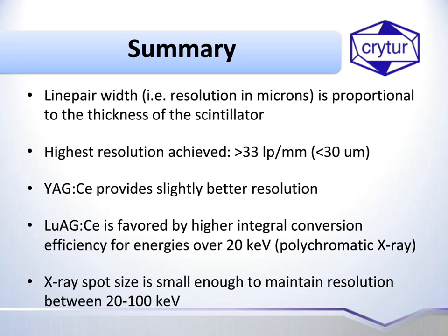But on the other hand, if the scintillator plate is not thick enough, it will not absorb all the radiation, so you will lose signal. So you have to think about signal-to-noise ratio and balance the thickness of the scintillator and its absorption to get the best result. And it depends on the application, which are different.